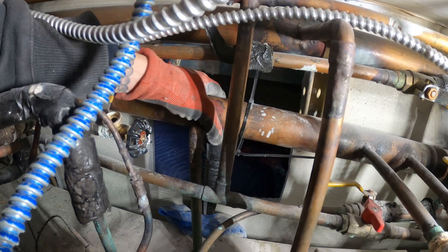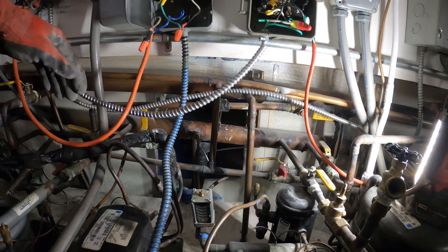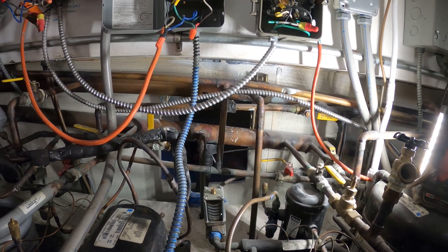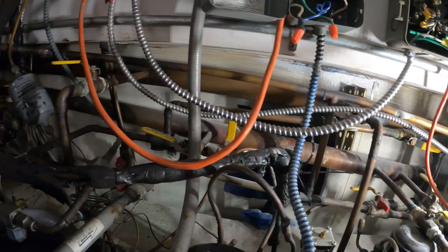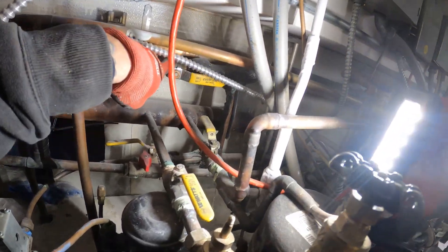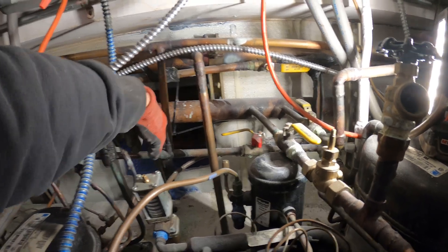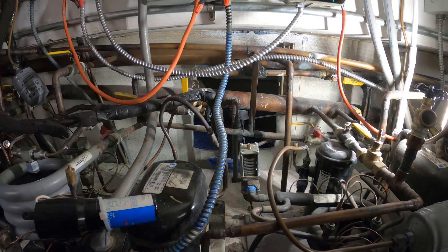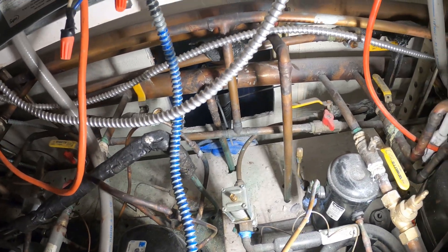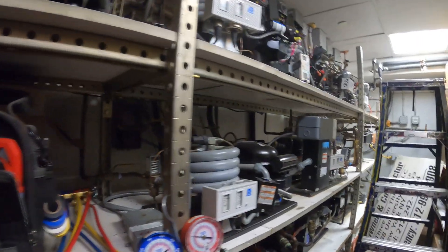The only thing I'm noticing right now is that there's no water coming out of here — this makes no sense. I know they recently heard something about the cooling tower having an issue where it kept losing water and they had to manually refill it. I wonder if this pipe is dry. Is that the supply or the return? Top one is supply, that's the return. I wonder if this pipe is literally empty right now and we're being starved of water. There might be bigger issues in this building than just this leak. Maybe there's water on the line but with no real pressure.